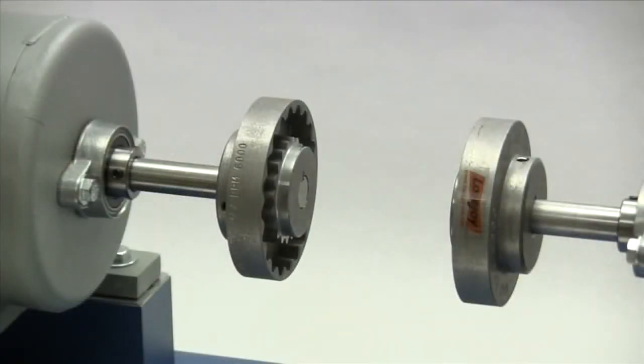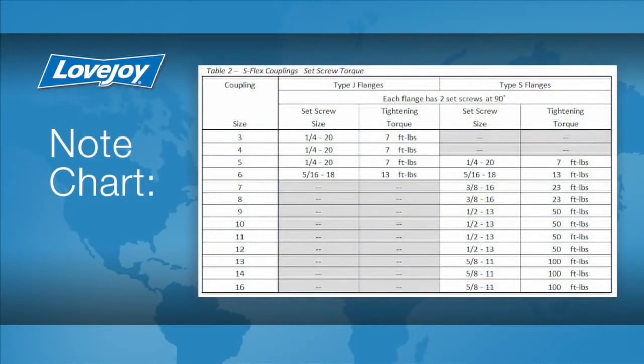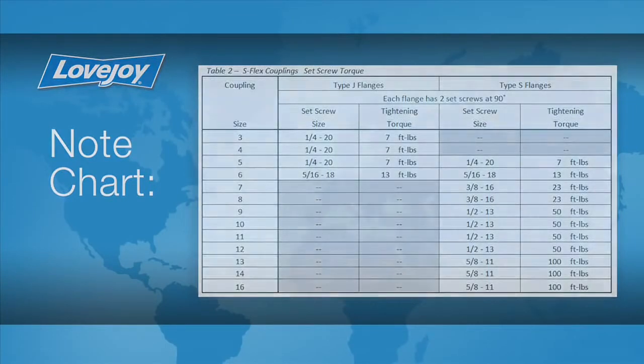Each S-Flex flange has two set screws and the set screws should be tightened with a calibrated torque wrench using the recommended torque settings found in the installation guide. The use of a torque wrench is important. If the set screws are not tightened properly, the flange could work loose and slide on the shaft. If the set screws are too tight, they could damage the key, shaft, or flange.